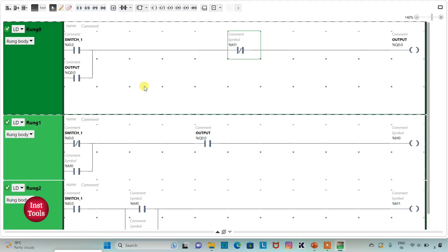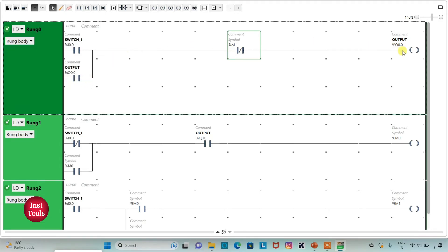So here, when switch1 is turned on, the current will flow through it. M1 is a normally closed contact, so in its false state, current also passes through it and output will be on. When switch1 is turned off, because we have latched the output here, current will still flow through it and output will remain on. That is, when switch1 is on and then turned off, output still remains on.